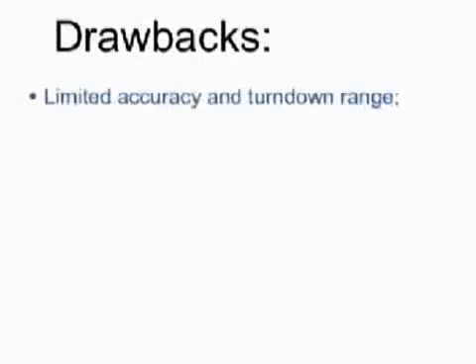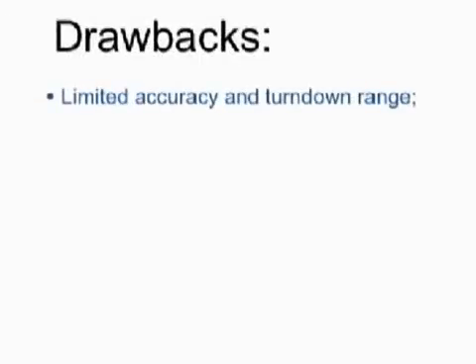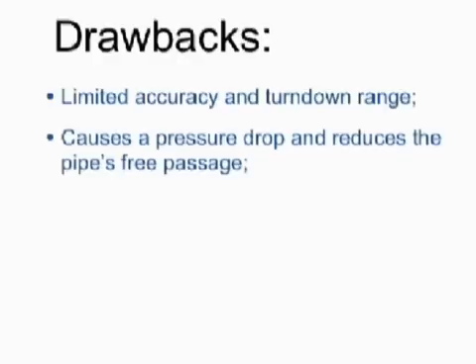Of course, there are drawbacks too. It has limited accuracy and turndown range. If high precision is your primary objective, there are probably better technologies. The orifice causes a pressure drop and reduces the pipe's free passage — as sensor technologies go, this is one of the more invasive. Ultimately, accuracy and turndown are related to pressure drop. In other words, the more accuracy and range you need, the greater pressure drop you'll have to tolerate.